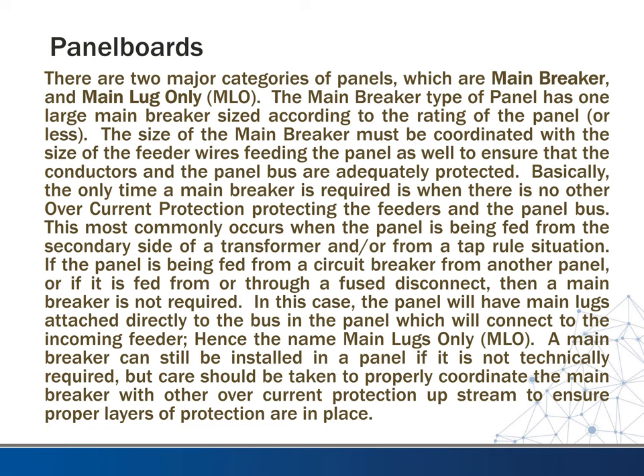In this case, the panel will have main lugs attached directly to the bus in the panel, which will connect to the incoming feeder, hence the name main lug only. A main breaker can still be installed in a panel if it is not technically required, but care should be taken to properly coordinate the main breaker with overcurrent protection upstream to ensure proper layers of protection are in place.